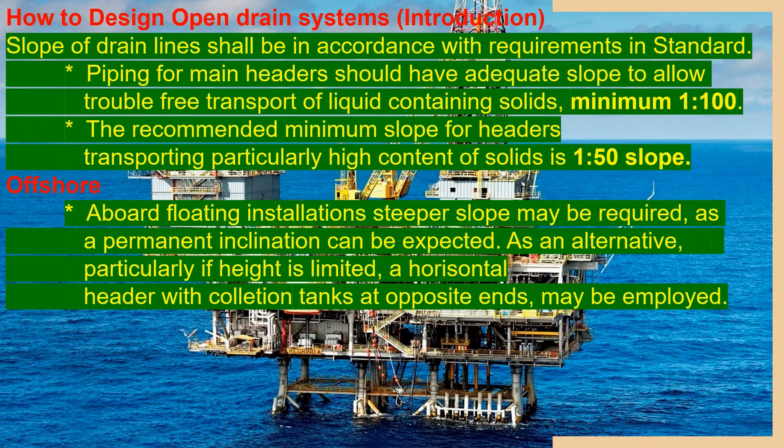Slope of drain lines shall be in accordance with the requirements and standard. Piping for main headers should have adequate slope to allow trouble-free transport of liquid-containing solids, minimum 1 to 100.